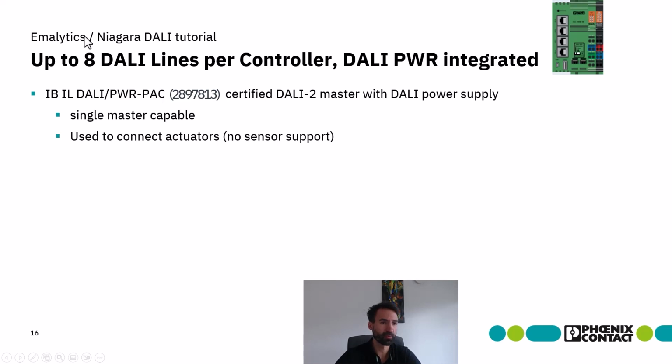Like I already mentioned, we can connect up to 8 communication modules to the ILC2050. So also 8 DALI lines per controller. And the interesting thing, the DALI power is already integrated into those lines over our terminal blocks.